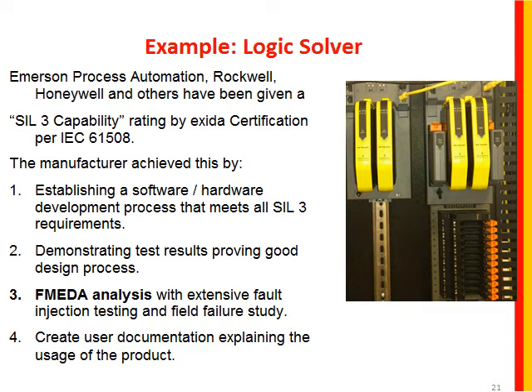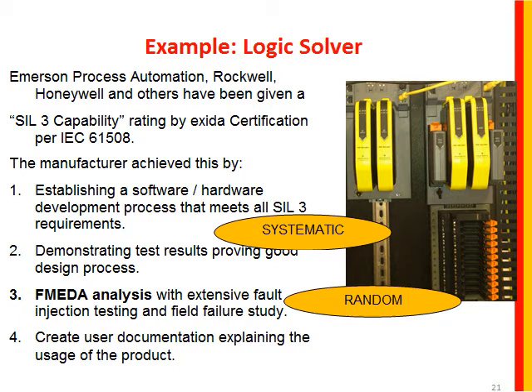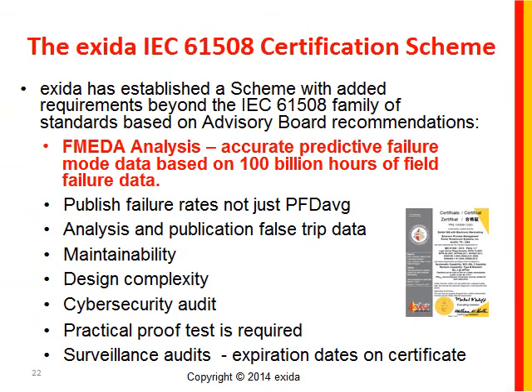Even logic solvers — the place where the whole certification concept began — are covered. I remember back in the mid-1980s when there was a huge argument about whether one could even use a programmable system as a safety logic solver, as opposed to relays. One of the problems with a relay-based approach is the false trip rate. Today, the fault-tolerant logic solvers made by many different manufacturers — including Emerson Process Automation, Rockwell, and Honeywell — have all had their logic solver products certified by Exida. We look for both random and systematic protection, which involves auditing their process, design, test results, performing a detailed FMEDA analysis, and reviewing end-user documentation.